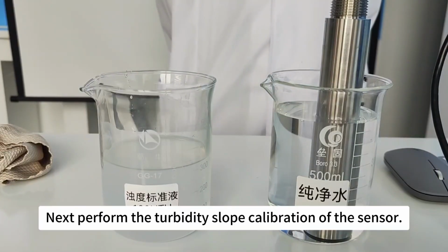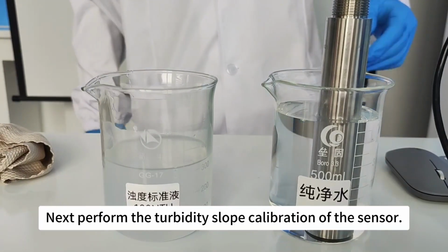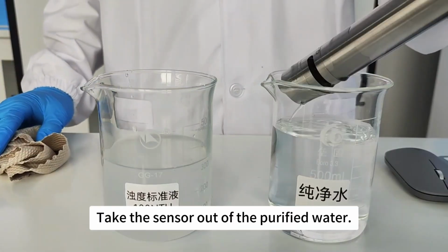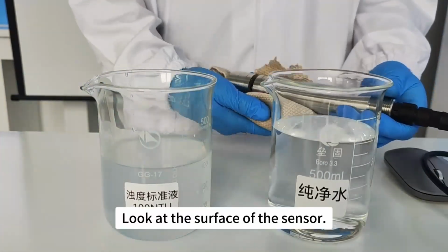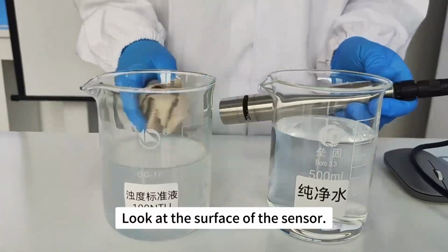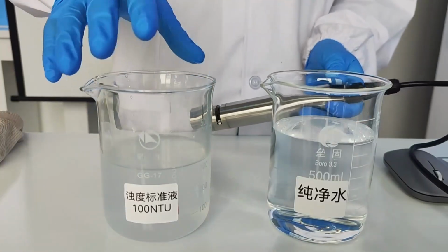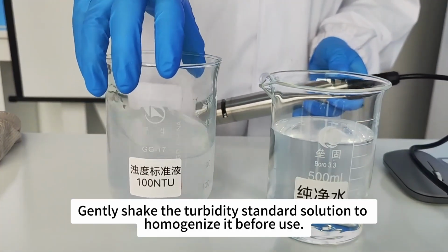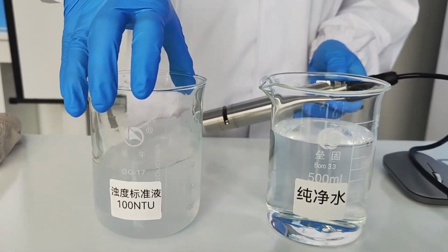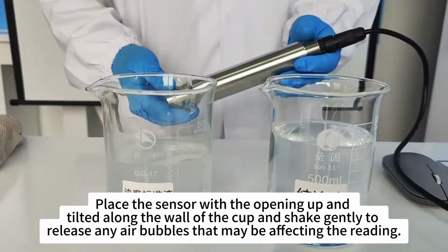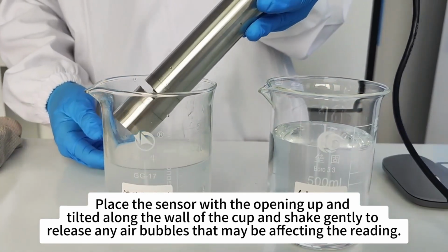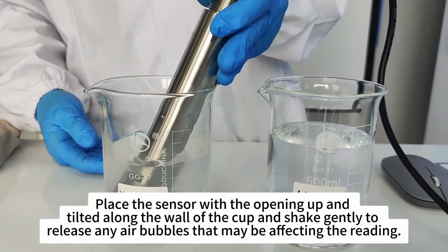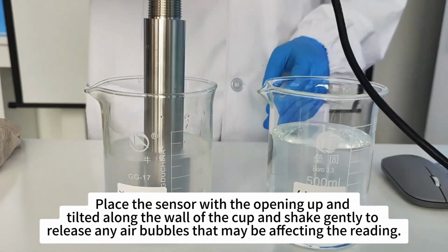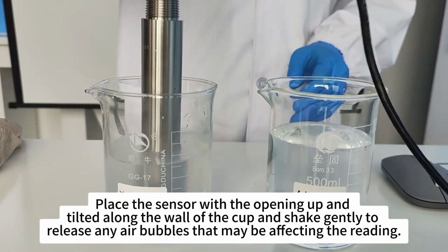Next, perform the turbidity slope calibration of the sensor. Take the sensor out of the purified water. Look at the surface of the sensor. Gently shake the turbidity standard solution to homogenize it before use. Place the sensor with the opening up and tilted along the wall of the cup and shake gently to release air bubbles and avoid affecting the reading.